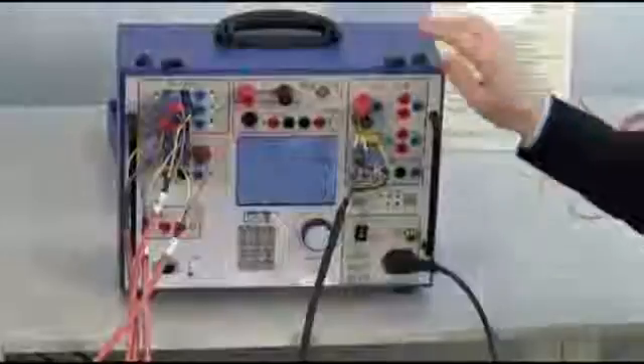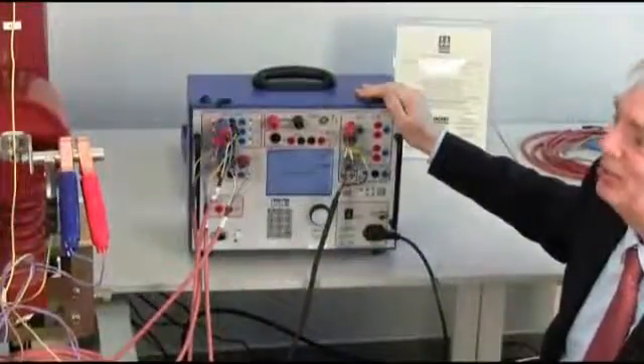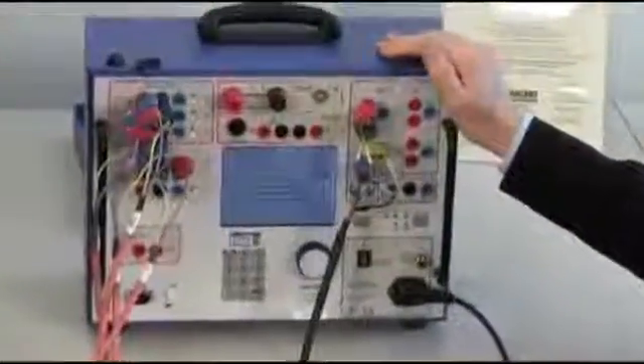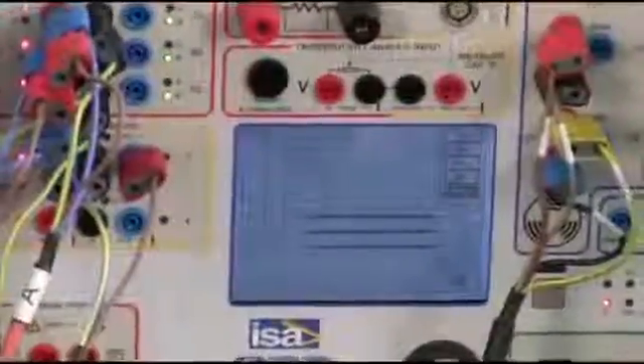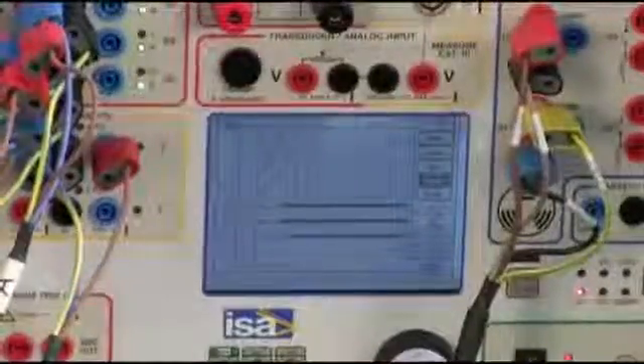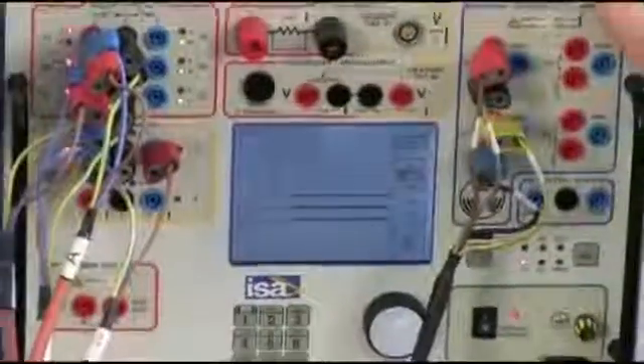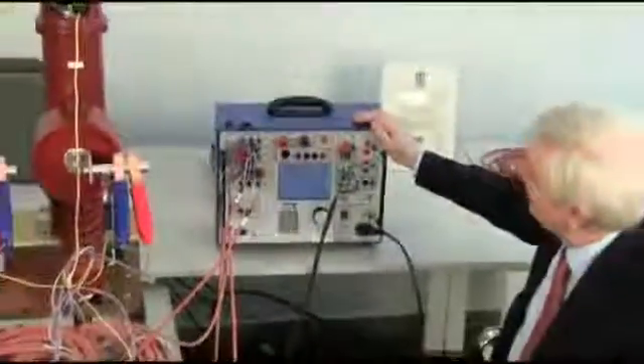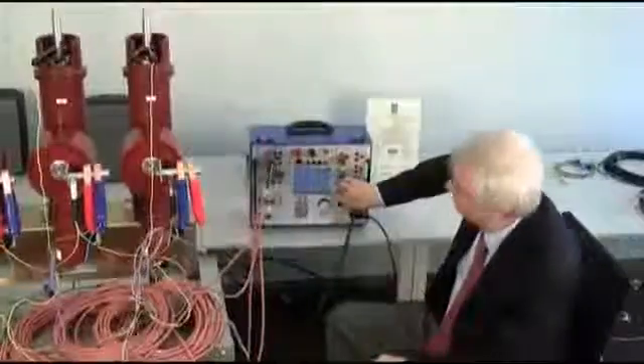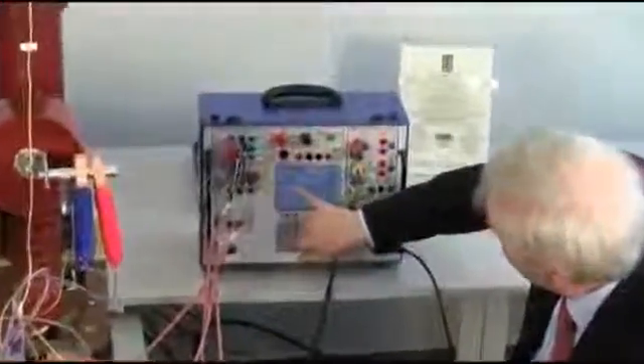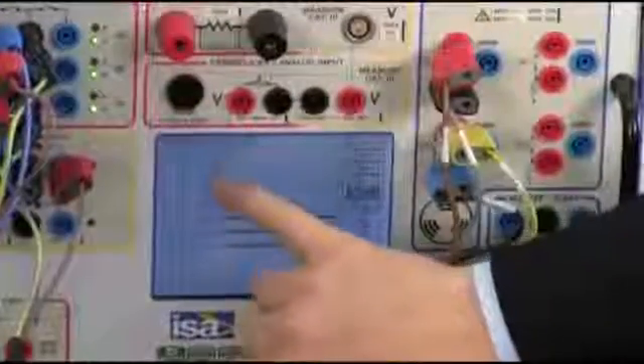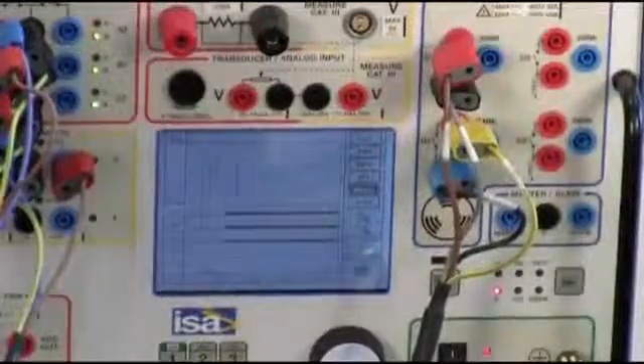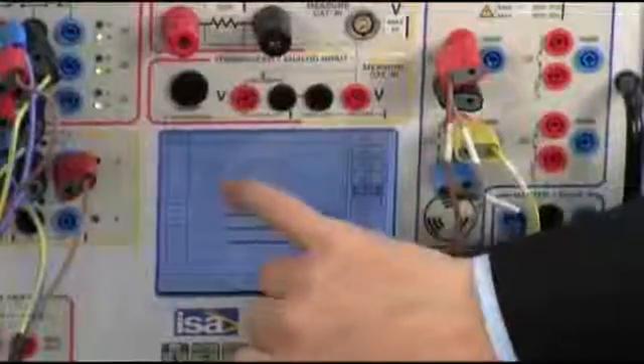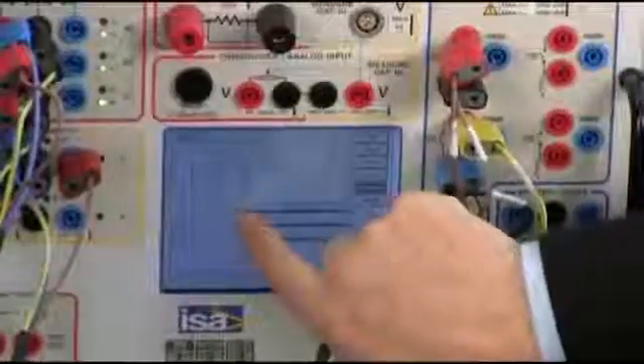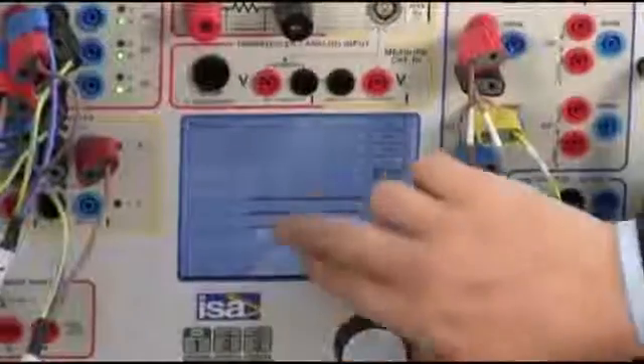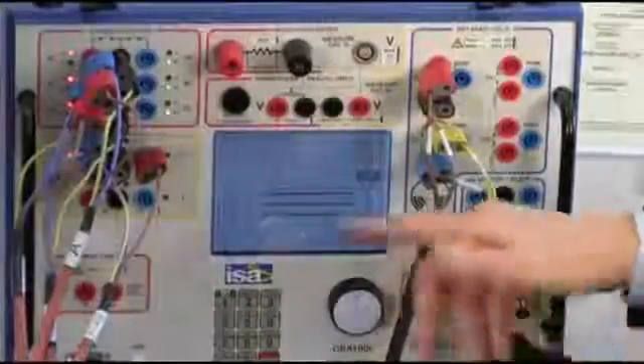The test is in progress. This buzzer is telling you that you are about to start the test. You are psychologically ready to the burst, to the big noise that the circuit breaker is doing during the operation. The noise that you have heard is, I believe, 1/10 as compared to a very high voltage circuit breaker. Okay, so this is the screen. On the screen, again, this is the default situation, is up here the current into the coil. You see, this is a typical shape. This is the moment where actually the trigger has been released. Next, you have here the recording of the three phases that have opened after, have closed after the close command.